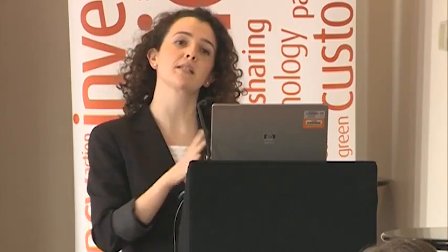Then the fifth thing is that we will take responsibility for managing this quota, and when we reach it, we will let you know. And anyone who connects after, because it's, I guess, the big question, right? What happens when we reach that? So anyone who connects after the quota will get curtailed first. So essentially, we go back to last in, first out, but after the whole block of megawatts pro rata have been connected.